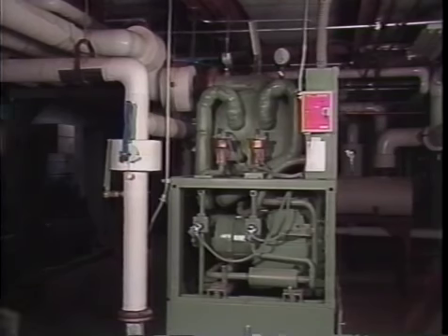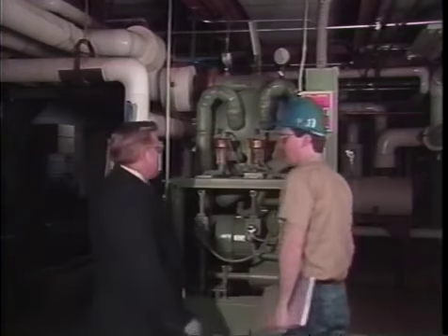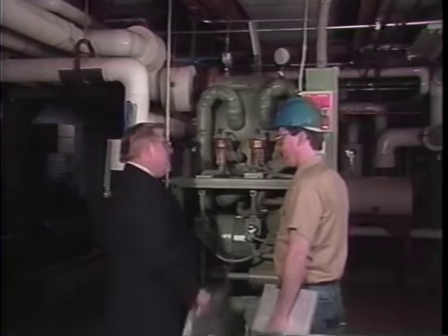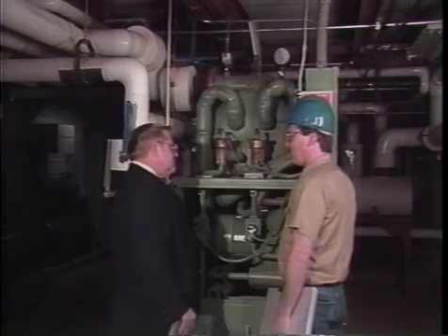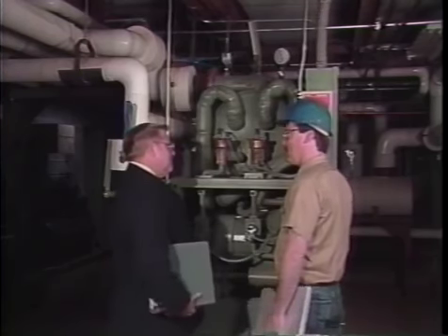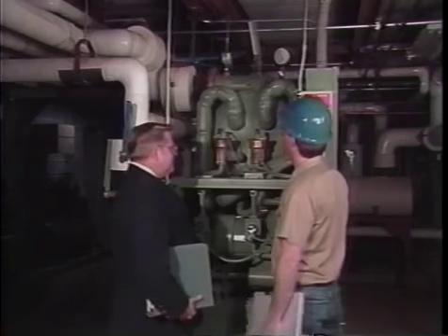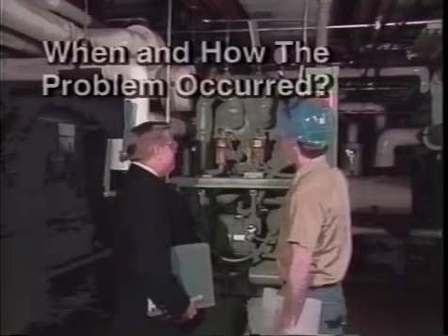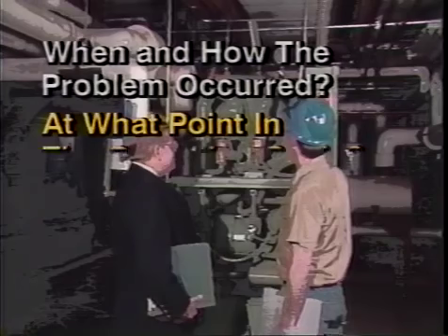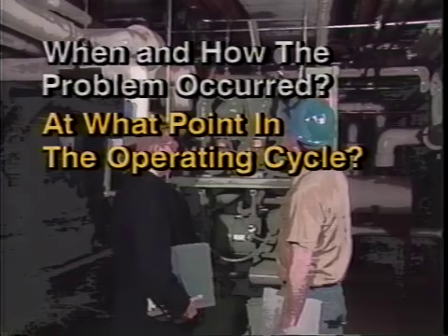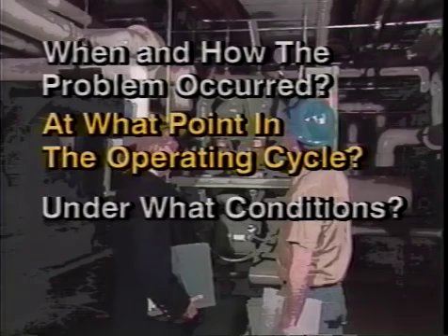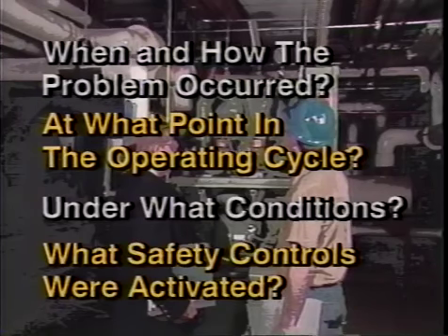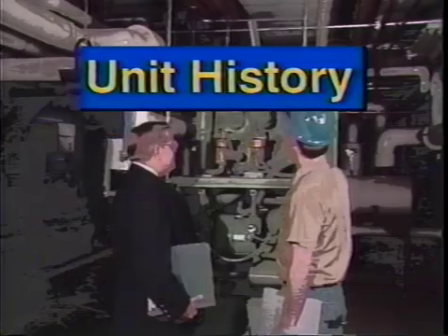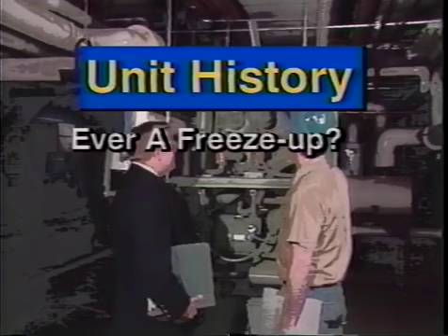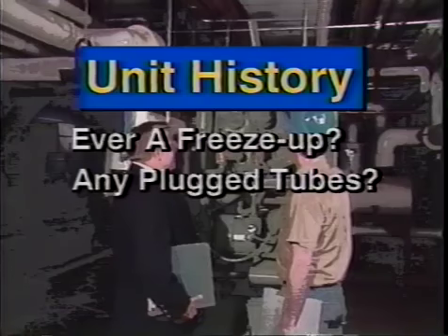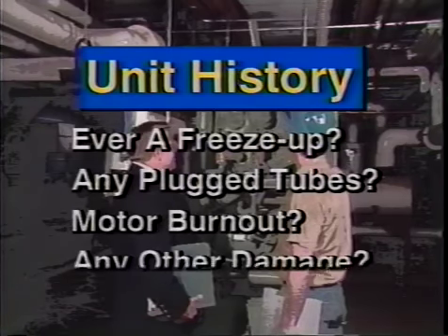The first thing to do is to talk to the customer or operator and review the chiller's maintenance history. You'll need information about the chiller. Start by asking pertinent questions of what happened. Learn as much as possible. Specifically, when and how the problem occurred, at what point in the operation cycle did the problem occur, under what conditions did the problem occur, and what safety controls were activated. You also need to know the history of the chiller. Was there ever a freeze-up? Any plugged tubes? Was there a motor burnout or any other damage to the chiller?